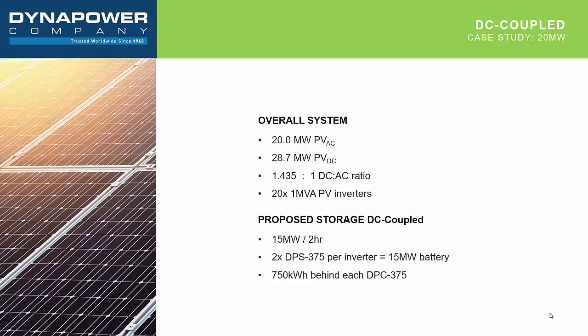In this particular case, there are 20 1 MVA PV inverters. So the use case for this particular application needed 15 megawatts of storage and 2 hours of storage. That worked out to 2 DPS 375s behind each 1 megawatt inverter, which gets us to the 15 megawatts of battery storage. And there's 750 kilowatt hours behind each DPS-375 to give us the 2 hours desired.